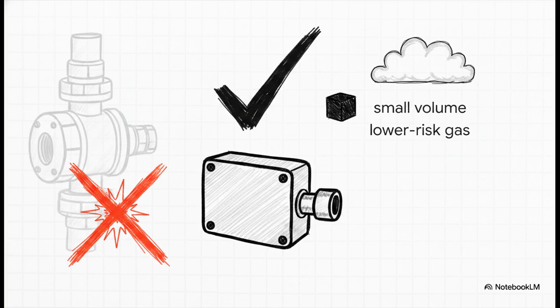You can absolutely use the standard compression gland here, because both exception conditions are met simultaneously. The gas group is IIB, which is not that high-risk IIC category, and the volume is 1.5 liters, which sits nicely under the 2-liter limit. But, and this is a big but, if you change just one of those variables, like if the plant suddenly upgraded to handle IIC hydrogen gas, boom, no way. You'd instantly need to rip that out and install a barrier gland.